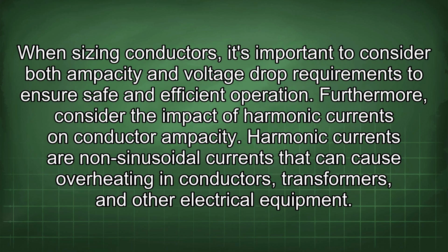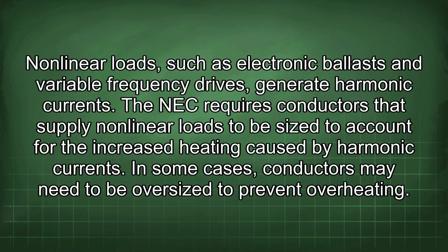When sizing conductors, it's important to consider both ampacity and voltage drop requirements to ensure safe and efficient operation. Furthermore, consider the impact of harmonic currents on conductor ampacity. Harmonic currents are non-sinusoidal currents that can cause overheating in conductors, transformers, and other electrical equipment. Nonlinear loads, such as electronic ballasts and variable frequency drives, generate harmonic currents.